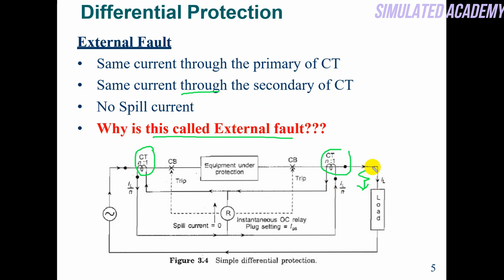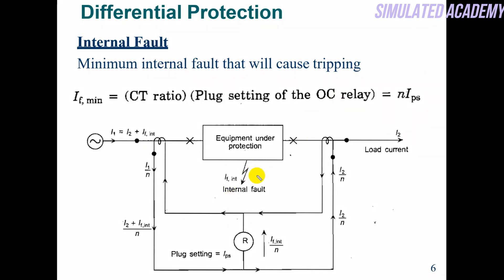If a fault occurs and a large amount of current flows, that current will pass through this CT and similarly pass through this CT as well. The spill current will be zero here, so this equipment will be under protection — relay will not operate. Now if an internal fault occurs, the current passing through CT1 does not pass through CT2 because it is grounded. So that current passes through the spill coil, i.e., the relay operates. Minimum internal fault causes tripping.